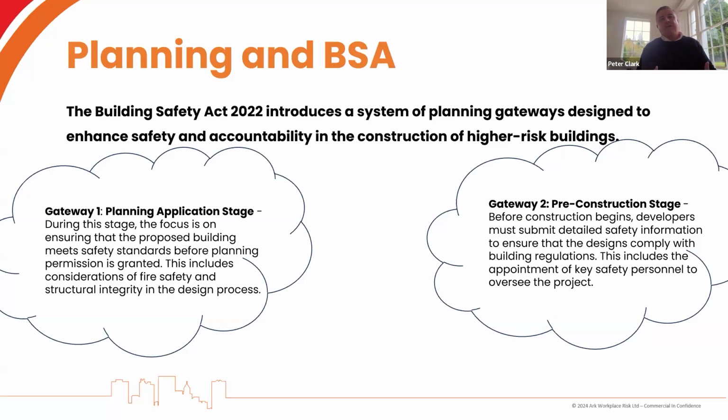This was interesting because the only existing document was a fire strategy which dated from 6 years before the building was occupied, and it didn't take into account the fact that in this huge building there are now 23 storeys of hotel accommodation. It just wasn't in the strategy. But the building got built, it got occupied, it got used, and it's a very safe building now, but you can see the problems that can arise from something like that.